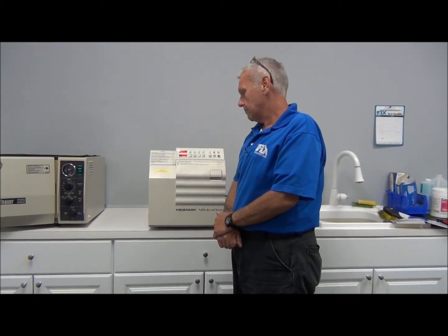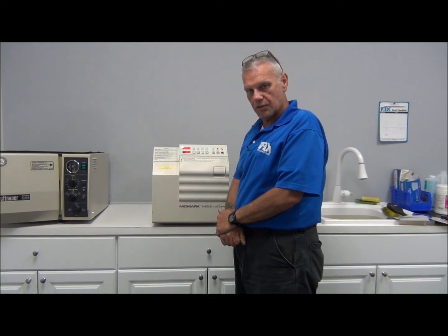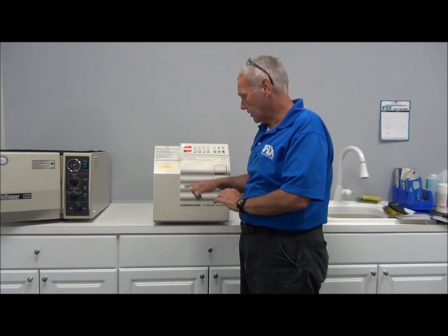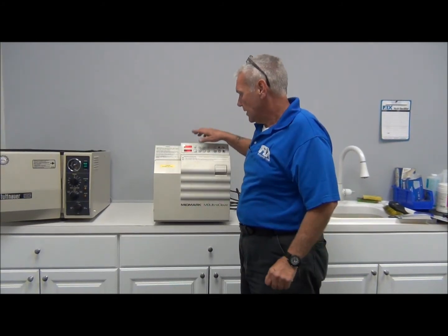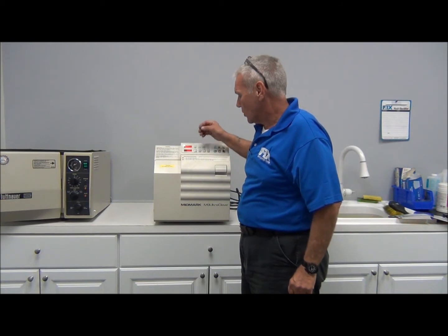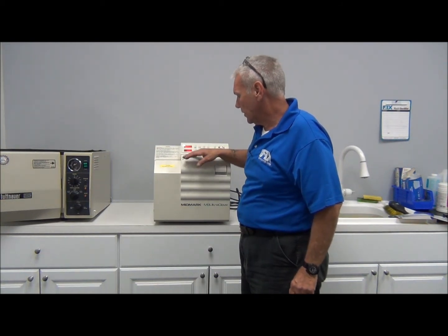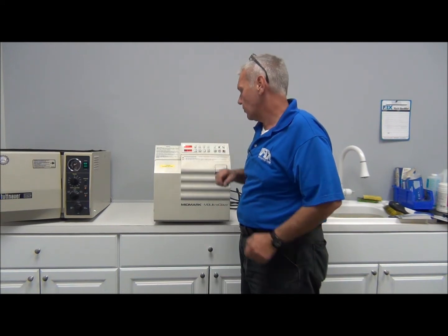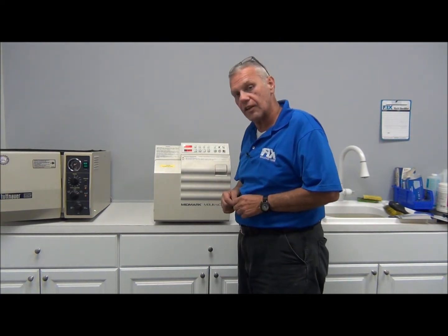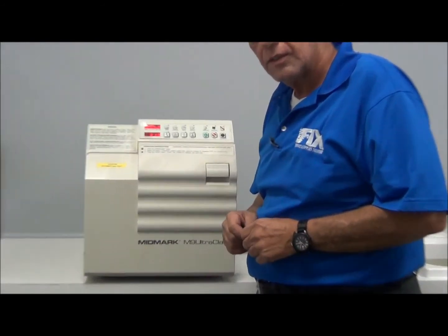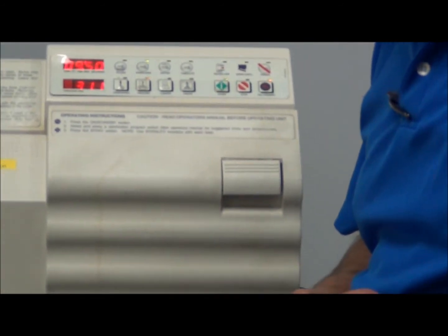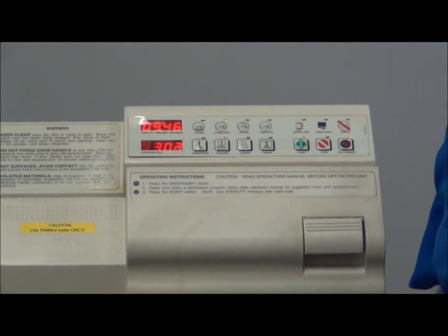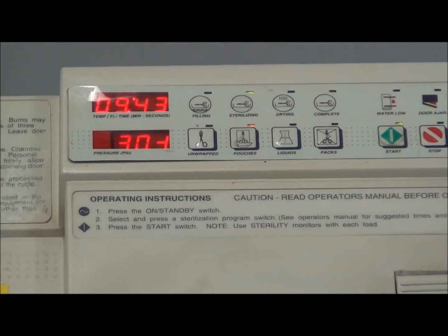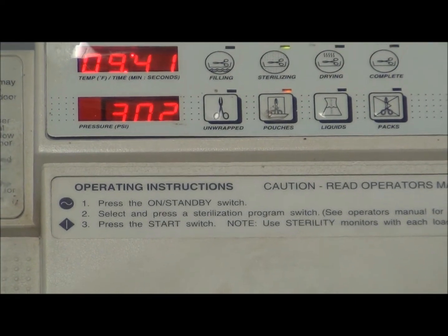Hey, we're back. We have pressurized the sterilizer. We're well into the sterile cycle. Inspecting the LED, you want to make sure all the LEDs and the numbers are complete. We're missing part of one of the numbers on the right-hand side, which does not affect the performance of the sterilizer, but it is a potential sale for a touchpad for you on this machine. Touchpad is available from RPI through parts at dentalfixrx.com.